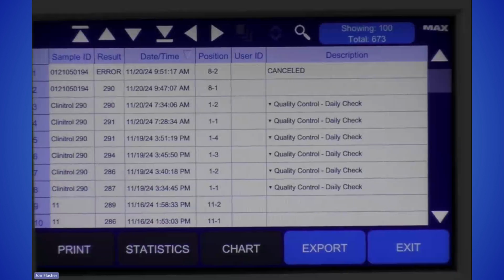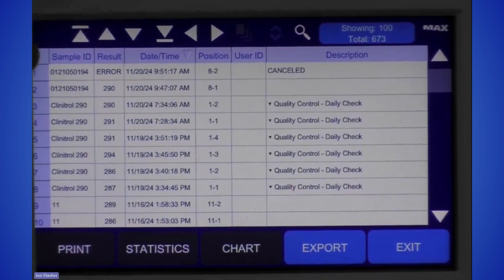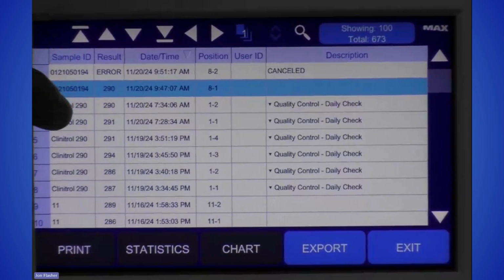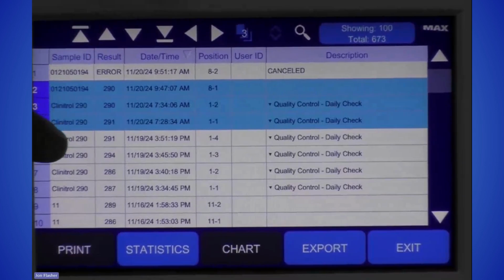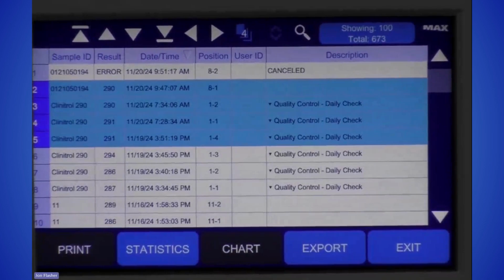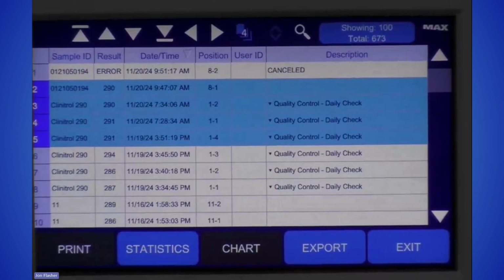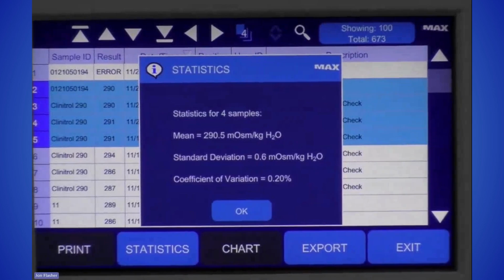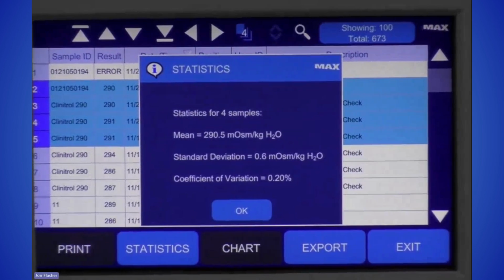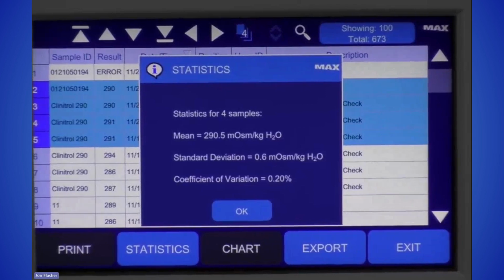All right, going back to camera angle number 2. You can see these results again. There are some other nifty features here on the result page. If I select a few results here, a bunch of Clinitrol 290 that I ran earlier on, you can see these 4 different results popping up on the result menu. You can perform stats. This little menu pops up when you hit that button, and it says that for these 4 samples you selected, you've got a mean of 290.5 milliosmoles, a standard deviation of 0.6, and a coefficient of variation of 0.2%. So pretty darn good.